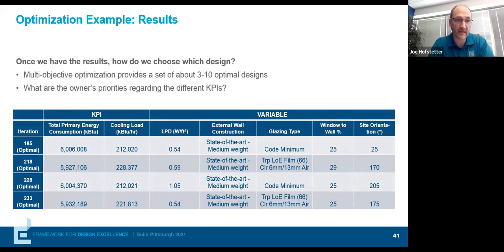The funny thing about those examples is we have 4 of those little dots down in the corner of the Pareto curve of our results. And you can see here, they get to those results all fairly close together in the first 2 columns of the chart, where we're right around 6 million kBTU annual energy use, and similar load characteristics on our cooling load.